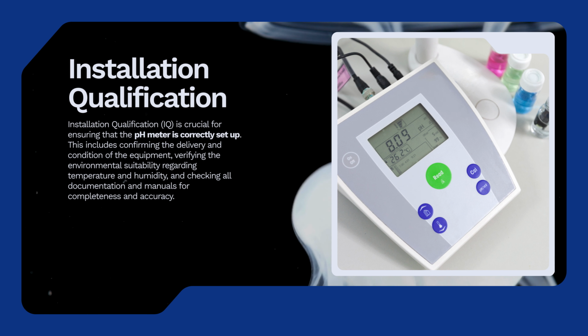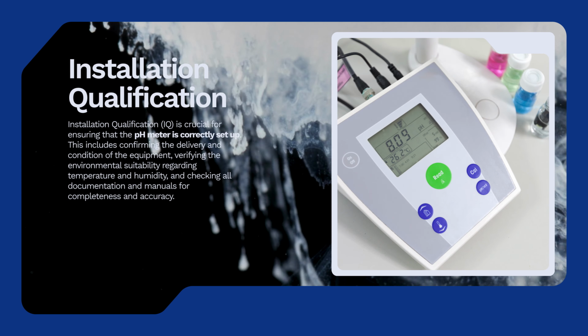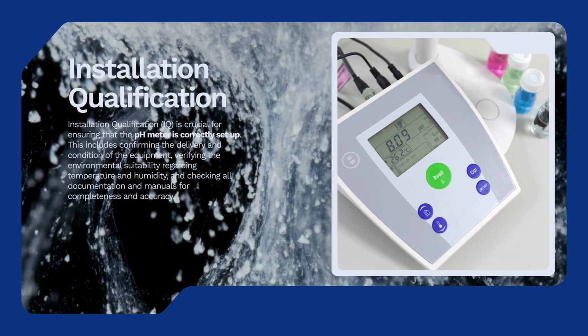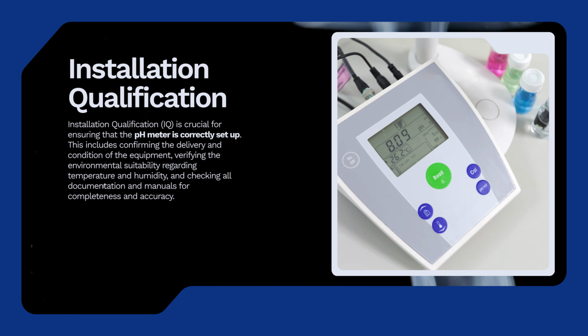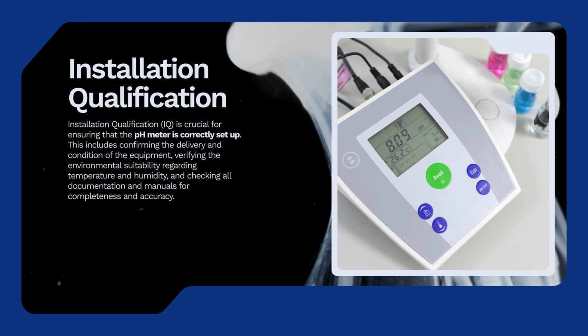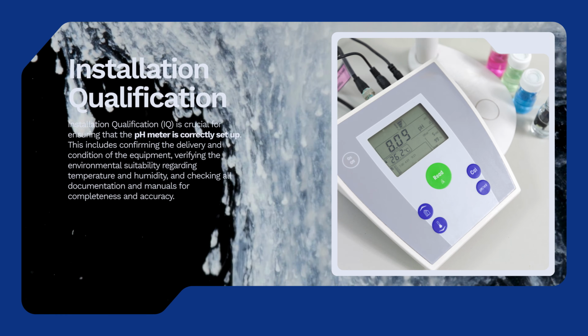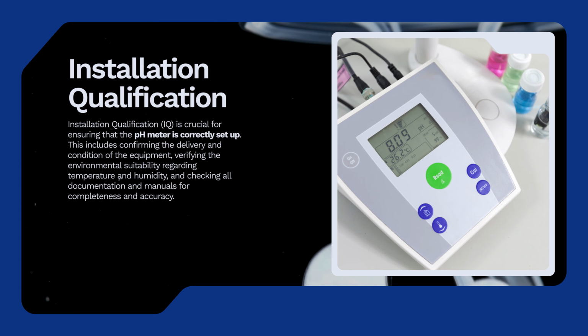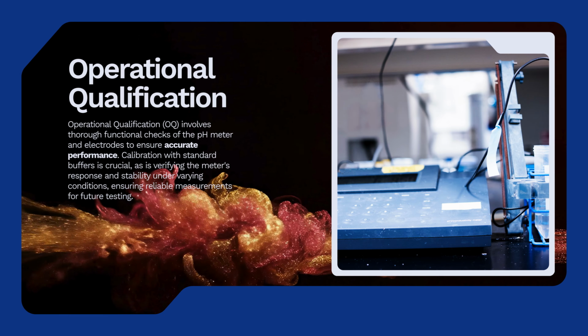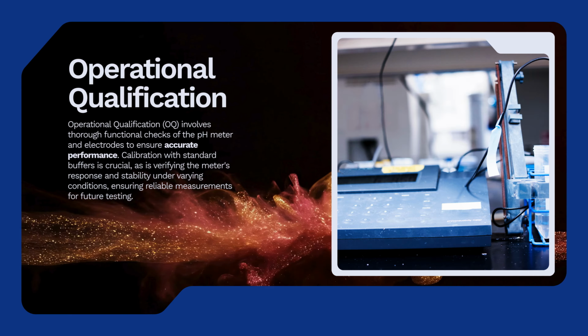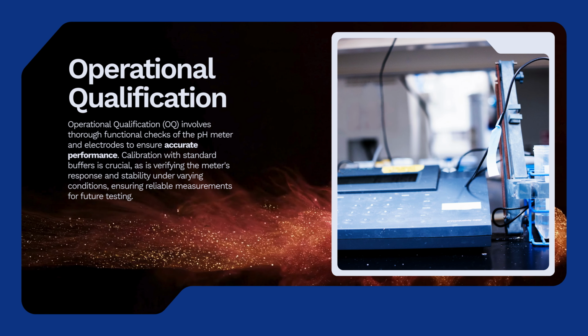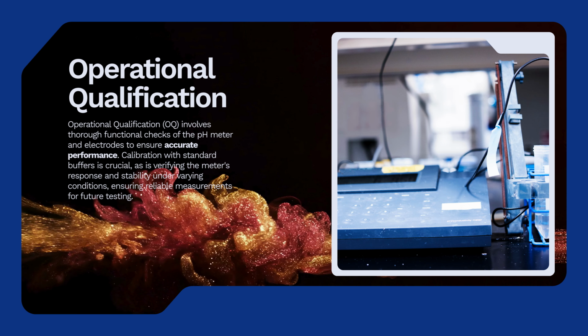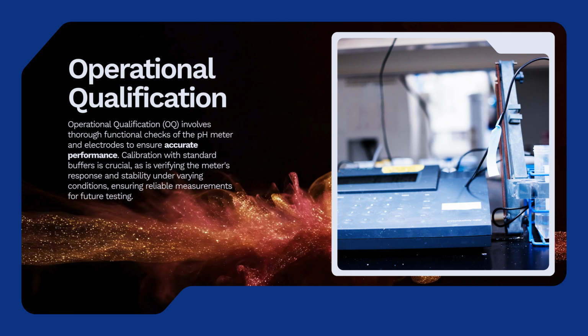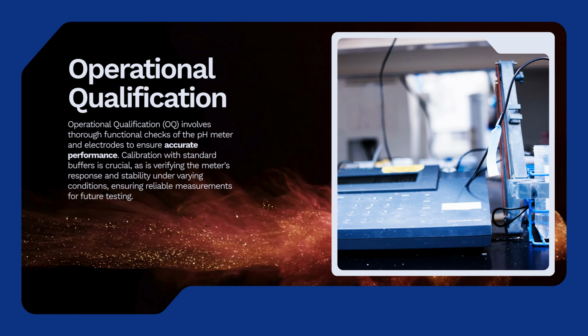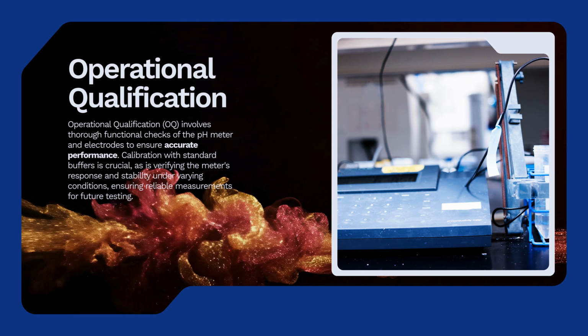During the installation qualification, or IQ phase, we formally confirm the equipment's physical condition and delivery status. We also verify that the laboratory environment is fully suitable regarding ambient temperature and humidity levels. Furthermore, we ensure that all technical manuals and required documentation are complete, organized, and readily available for the end users. Operational qualification, known as OQ, involves a series of functional checks to ensure the meter and electrodes perform exactly as intended by the manufacturer. Using certified, standard buffers for calibration is absolutely crucial during this stage to verify the meter's electronic stability and its response time when subjected to varying chemical conditions in the lab.